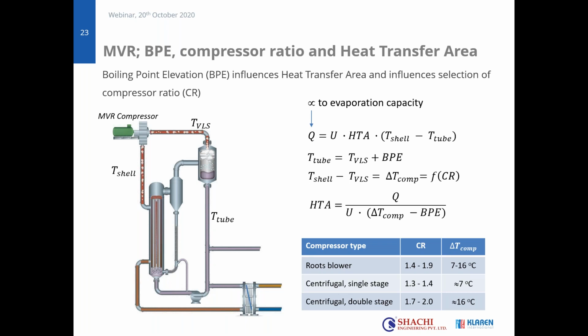In the design, boiling point elevation will affect your heat exchanger design. This is really something to carefully consider. For this I need some equations, so allow me in this webinar to go a bit deeper. If you look at the capacity of the heat exchanger, the capacity of the MVR unit, you talk about the heat duty. The heat duty is the heat transfer coefficient times the heat transfer area times the difference in temperature between the shell and the tube. The duty also is related to the evaporation capacity. So if the evaporation capacity is, for example, 20 kPd, you can calculate how much kg per second that is, and you can derive how much heat duty the heat exchanger needs to pass.